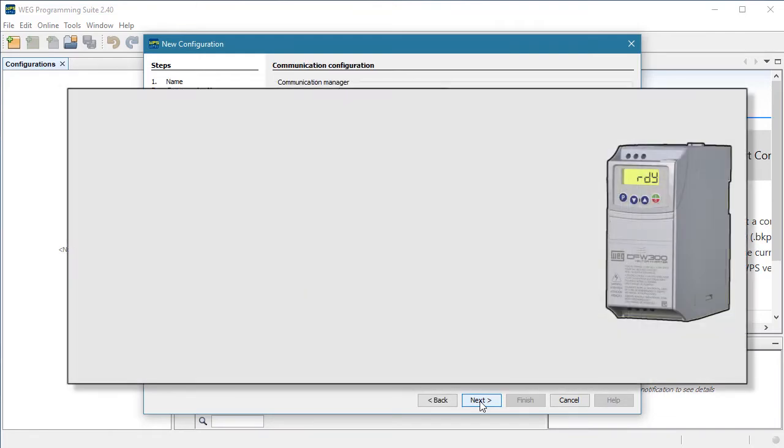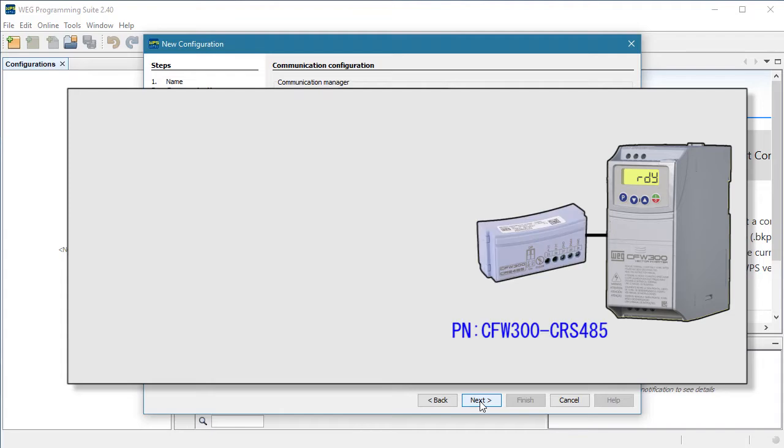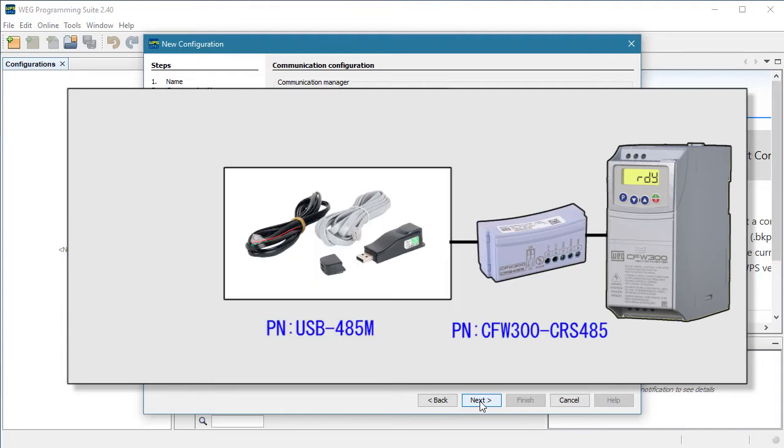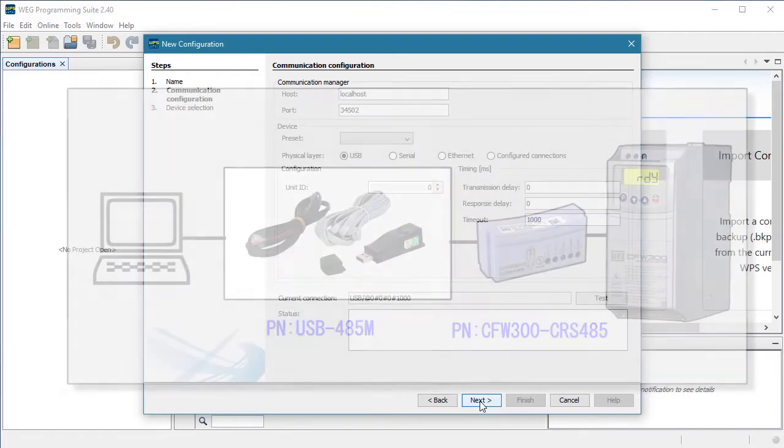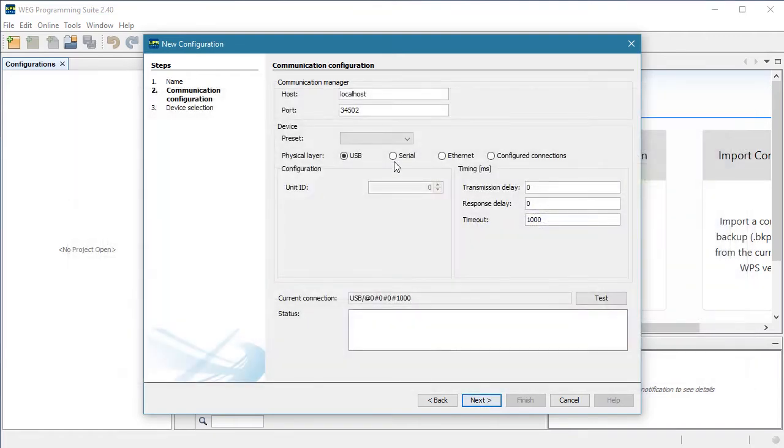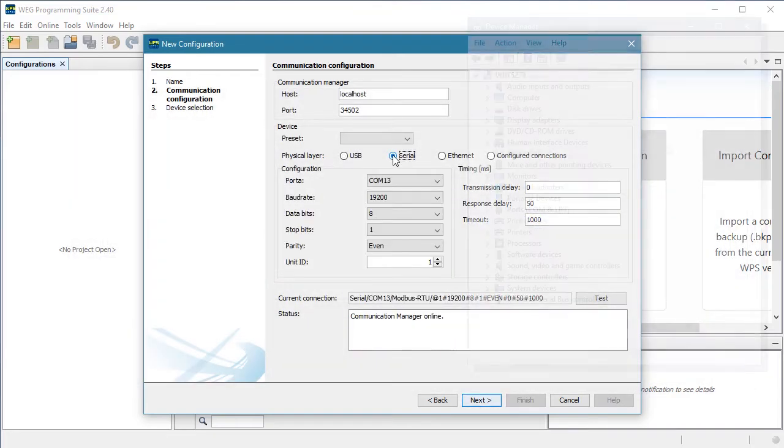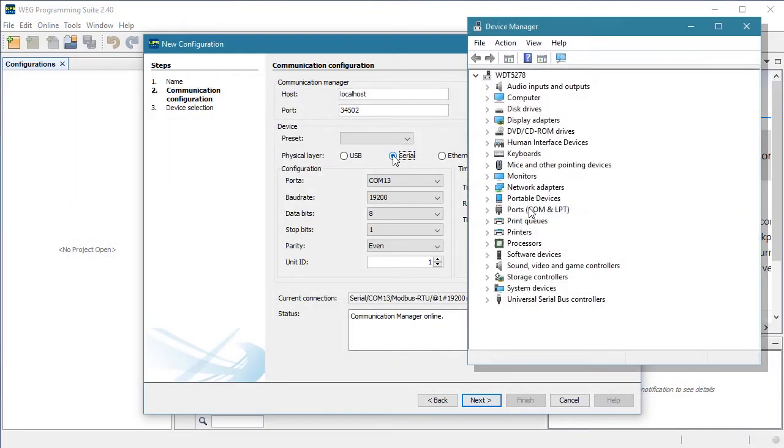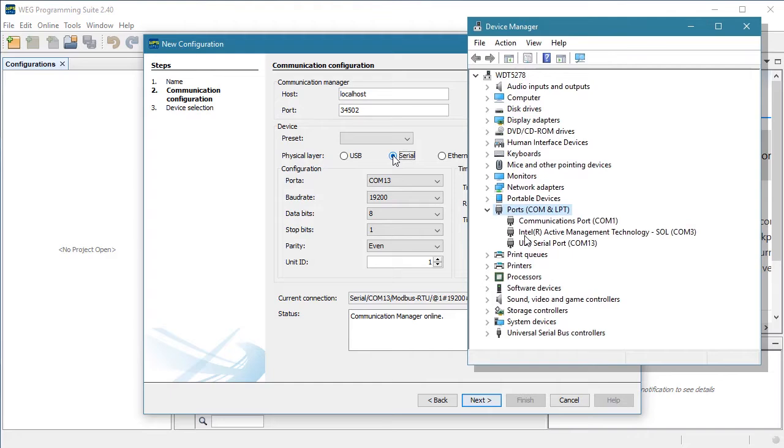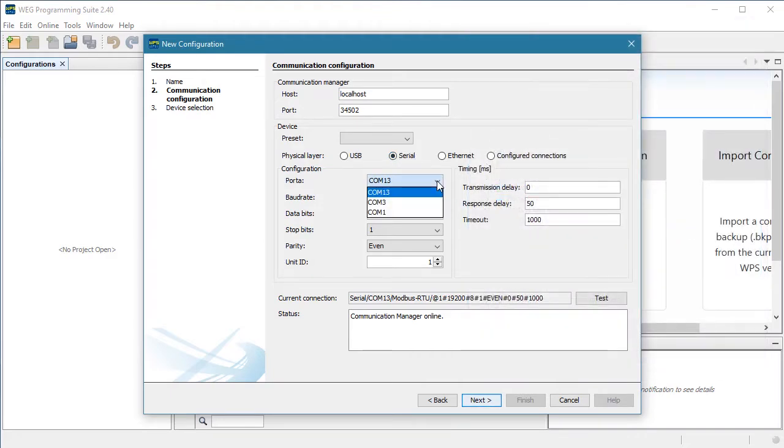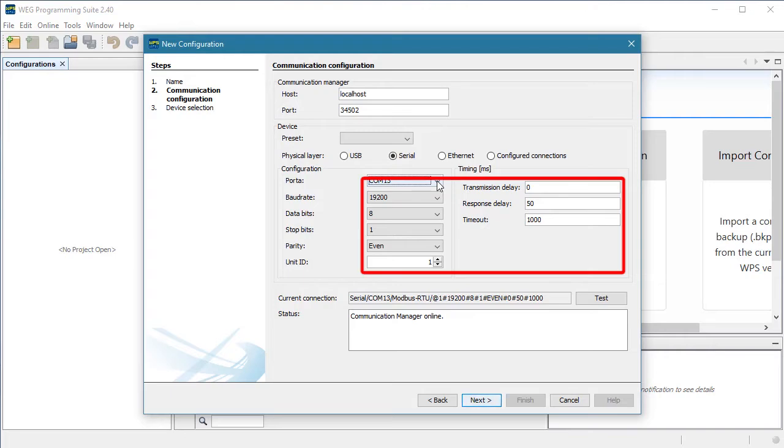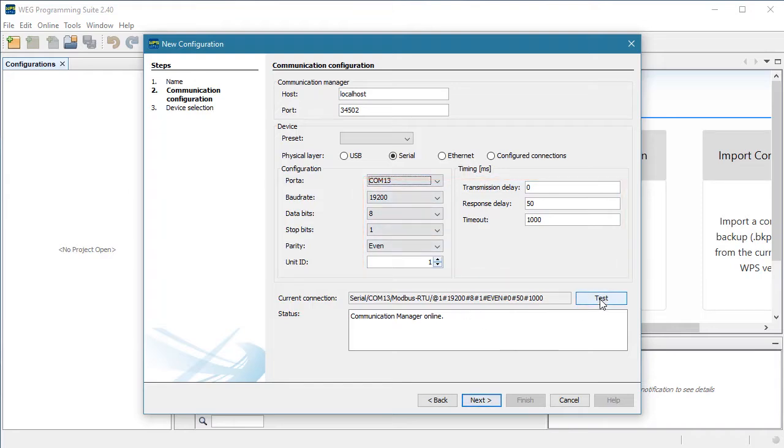I am connected to the drive using this RS-485 COM module and this USB to 485 converter which to my PC looks like a serial port so I choose this. I see in my PC's device manager that the drive is on serial port 13. The rest of these are the drive's default values and since we just did a factory reset, I know these are what I need so I'll hit test to make sure WPS can see the drive. It does so we hit next.